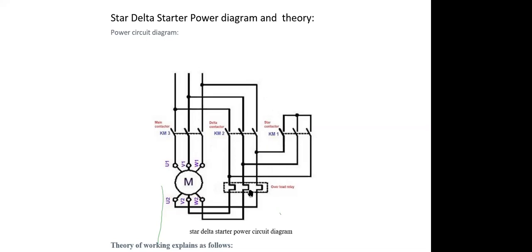As I say, this overload here is also in series. And I will definitely say one important thing. When you are doing an overload relay setting, please keep in mind it is a phase current setting, not a line current setting. We know the relation between line current and phase current: it is 1 by root 3, that is 1.732.